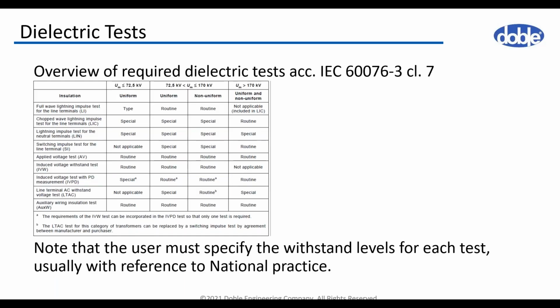Back to you, Stefan. The purpose of the dielectric test is to verify the dielectric capabilities of the transformer isolation system. The required dielectric tests and the test voltage level depend on the highest voltage for the equipment, or Um. The required tests are summarized in the table displayed, and the classification defines three categories. The first one is up to 72.5 kV, the second one from 72.5 to 170 kV, and the last category is above 170 kV. The withstand level for each test should be specified by the customer, and usually it is based on the national practice.